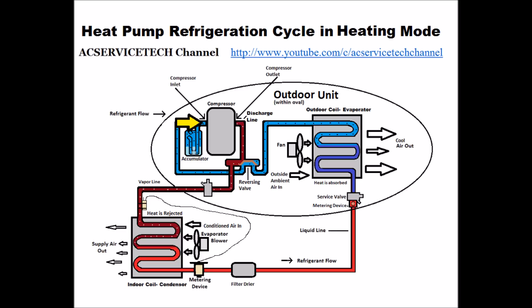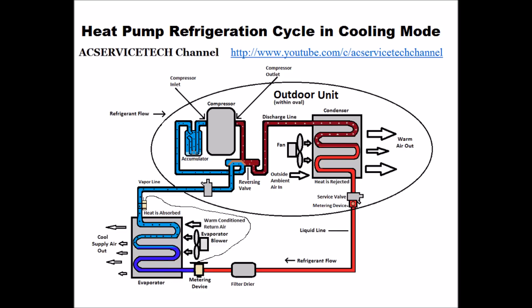The cycle starts all over again — low pressure vapor comes in, high pressure, high temperature vapor comes out of the compressor. Now we're going to move on to cooling mode and look at the superheat and sub-cooling occurring in the coils. What changes the direction of refrigerant flow — for most major manufacturers besides Ruud and Rheem — is powering 24 volts to that reversing valve.